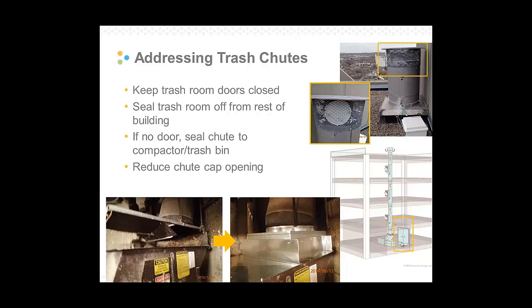If there's no door or no room that's isolating the chute from the building air, this is common on the dumpster room floor, so on the bottom floor. We'll see where there's not really a separate room for the dumpster to be in. Maybe there's storage areas down there, office areas, lobby, that's allowing chute air to access building air. If that's the case, we did a retrofit in one building where that was the case, and we enclosed the bottom of the chute. You can see the picture on the left was the before. The picture on the right here at the bottom is the after. We enclosed the bottom of the chute to the top of the dumpster to isolate the building air from the chute air.